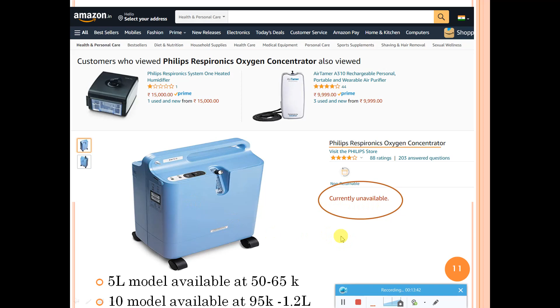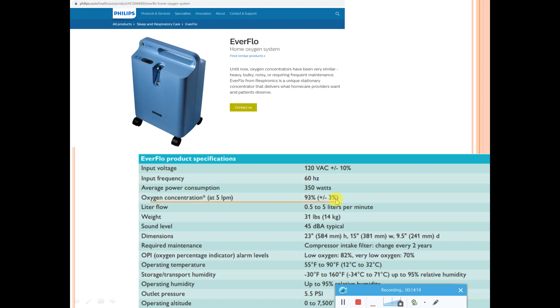So this is what I'm telling you about the specification. So just have a look here. This is the specification of this particular product, and here you can see the oxygen concentration, 5 liter per minute. Okay, so this product is at 5 liter per minute, but you can see the concentration here, 93% plus or minus 3, which is good enough. Okay, so that is why this is a good product. But sometimes some brands will show you 5 liter per minute, but there it is 20 to 30%, which is not good. So you have to check the specification sheet of the product and only then decide to buy.